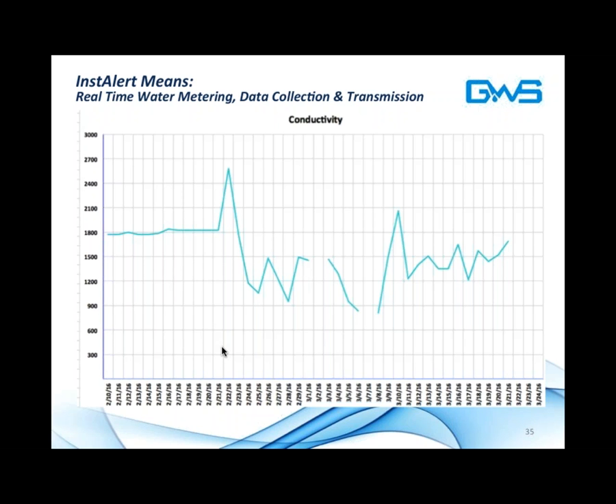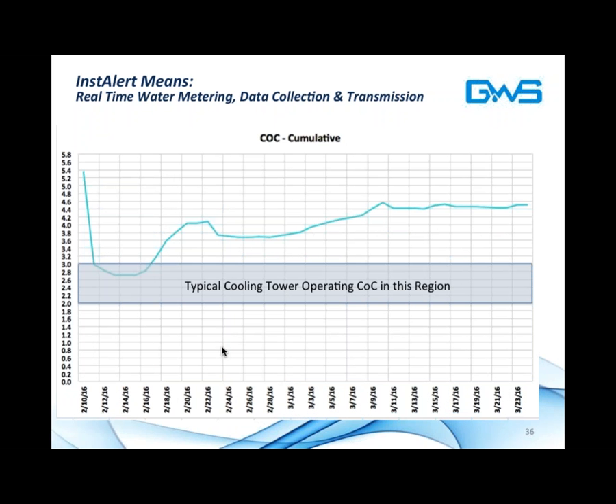We understand that a lot of these spikes and dips have something to do with system operation, in some cases rain, which actually will dilute the conductivity of the cooling tower. This matches up with weather reports and specifically the data on site with the customer. Cycles of concentration, which are cumulative here, is also something we can determine as a result of measuring inflows and outflows. You can see the typical cooling tower operating cycles of concentration will occur between 2 and 3 cycles in this part of Southern California with very hard water.